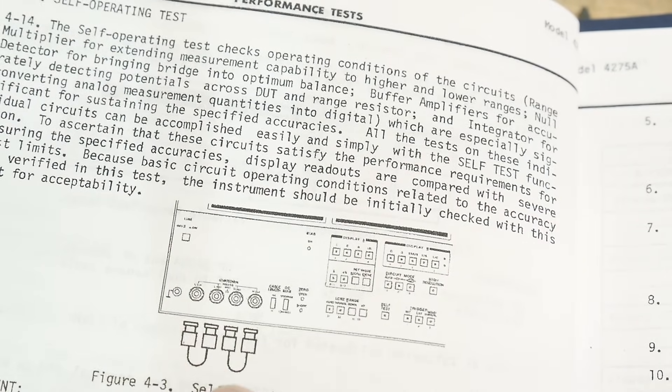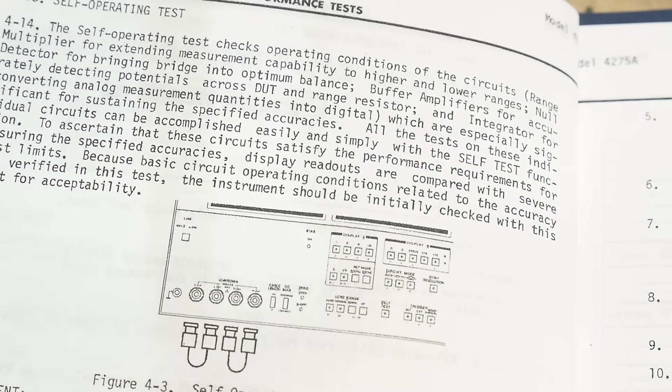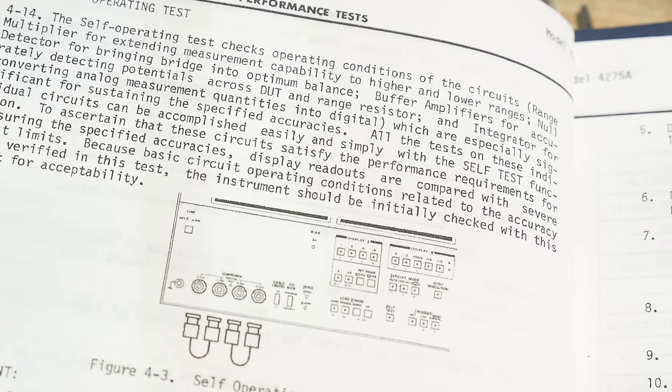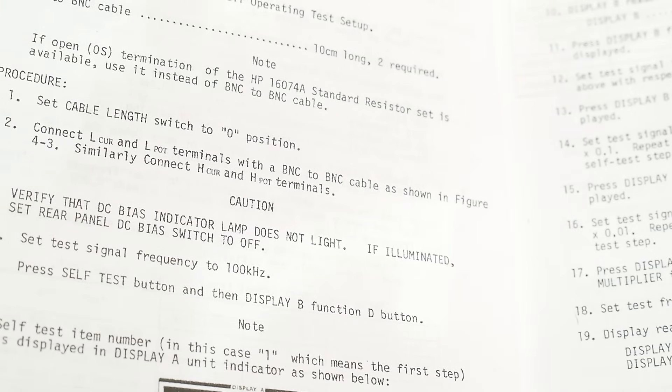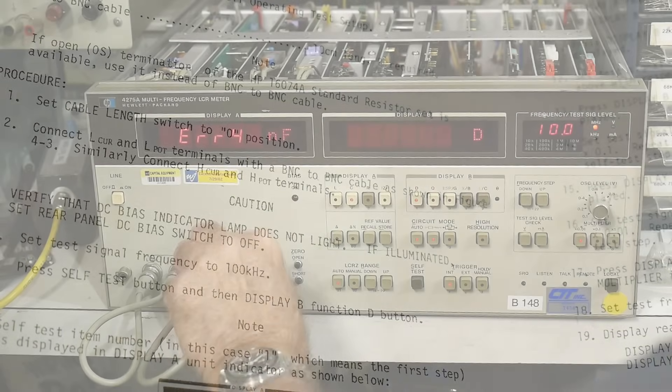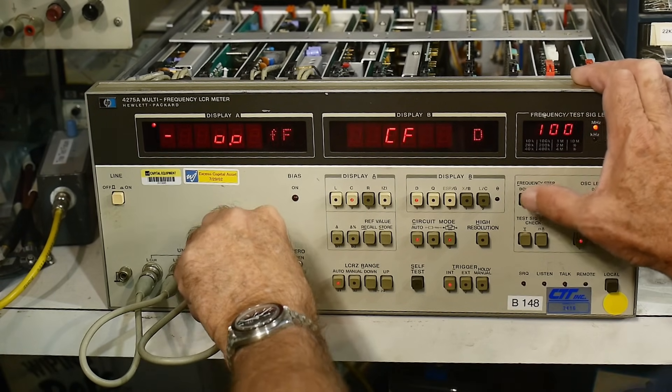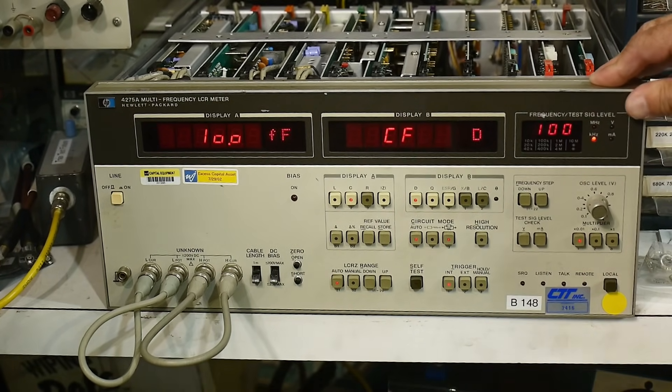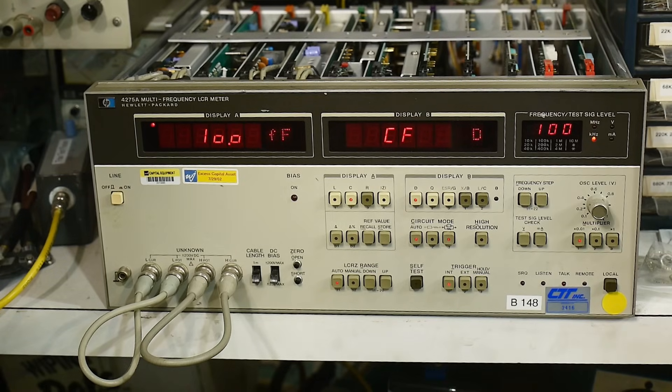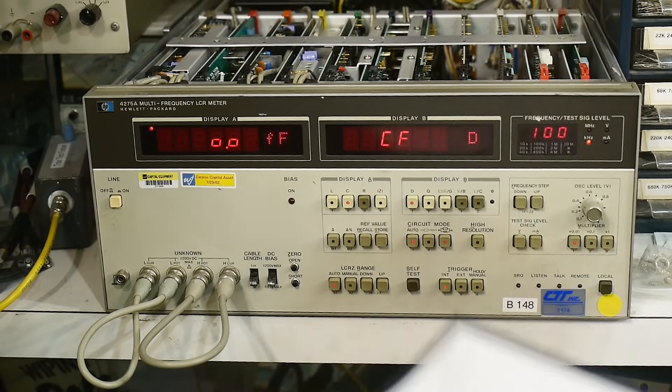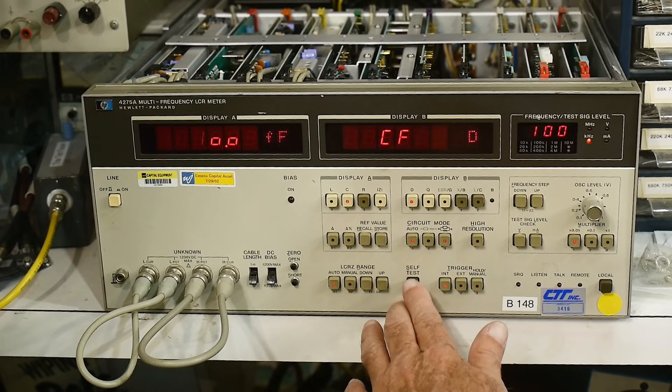Go on to the next test. Self-operating test, we need some BNCs that go like that. Connect cable length is zero, connect terminals with BNCs like that, test frequency to 100 kilohertz. Press the self-test, and then the B button, function D button. Let's hook this thing up. 100 kilohertz, it said.